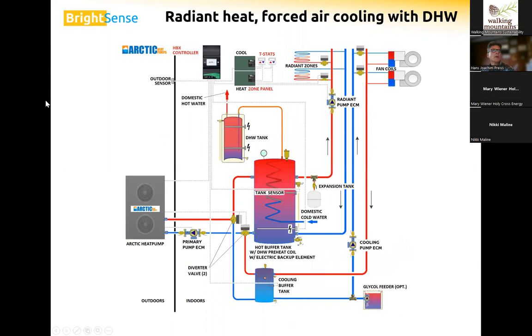I also get the question a lot: can I heat my domestic hot water with this heat pump? And the answer is yes, you can, but it makes the system a lot more complicated. You need a tank with a domestic hot water coil. And if you wanted to do cooling, then you would definitely need a separate cooling tank, because we want to heat this tank all the time. We can't cool it, otherwise it would cool our domestic hot water. So it adds significant complexity and it adds cost. These tanks with the coils are expensive. They're not cost effective at this point.